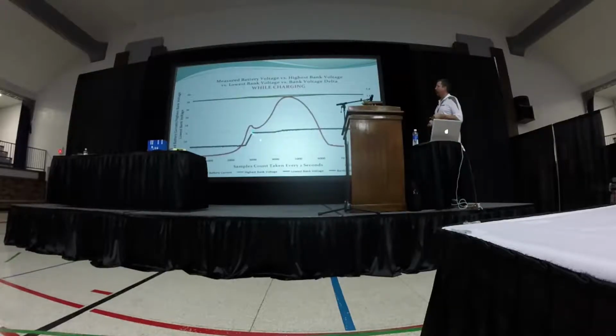So probably right around in here, where you see the current on the EVCON drop down to near 0, this green line right here is our highest bank. No doubt, right about that point in time, it got to about 41.5 volts. And we taper the current on the EVCON to maintain that 41.5. As soon as it goes above that, we shut off the EVCON, which happened right here. Well, not completely shut off. It was probably about 2 to 3 amps of charge. And then we let the little laptop chargers take over.